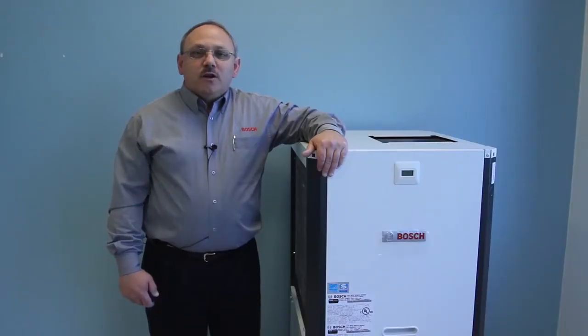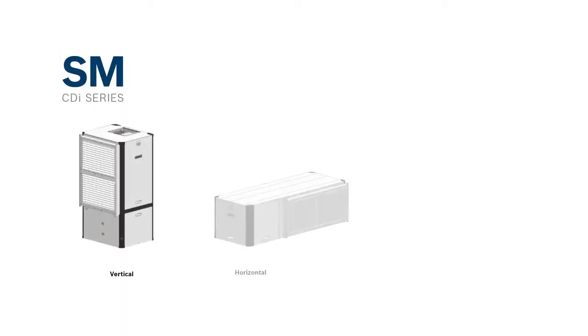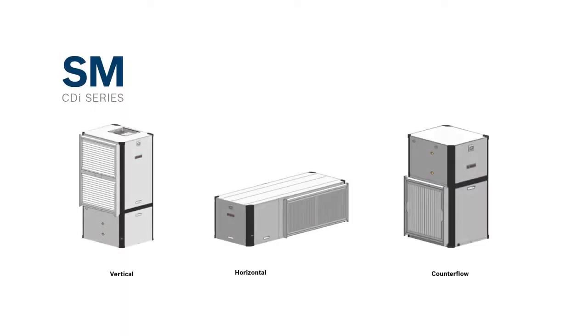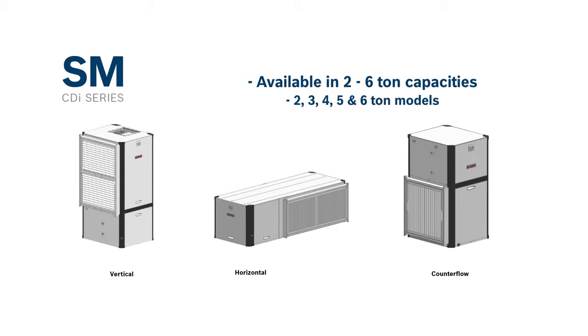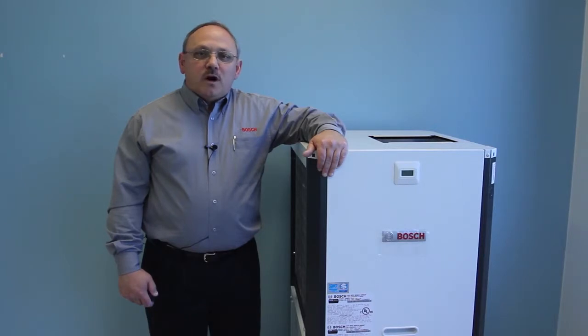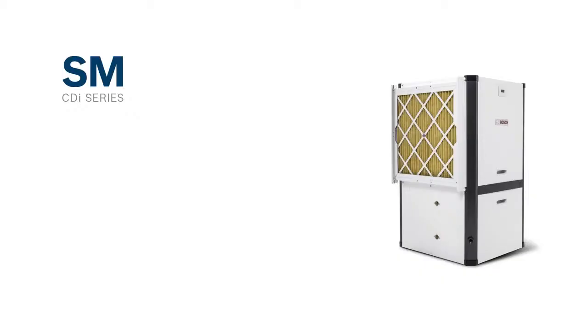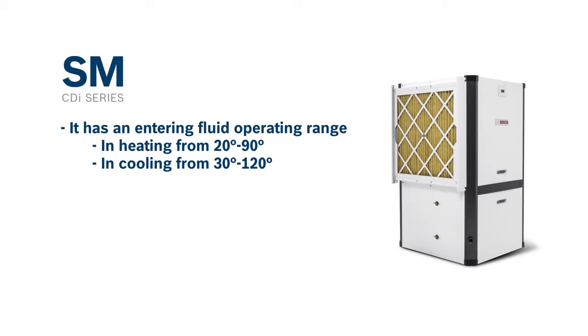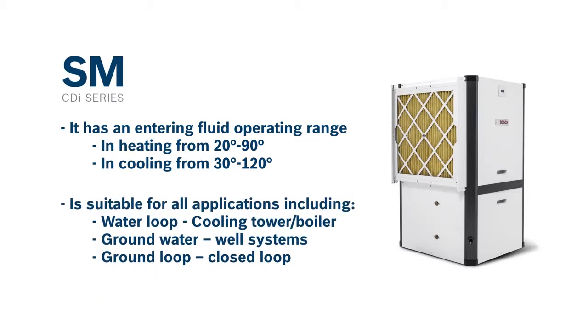It is a water-to-air heat pump. It is currently available in vertical, horizontal, and counterflow package models. It is available in capacities from 2 through 6 ton, and this video will cover the vertical model you see here today. It has an entering fluid operating range in heating from 20 to 90 degrees, in cooling from 30 to 120 degrees. It is suitable for all applications, including water loop or cooling tower boiler applications, groundwater or well water systems, and then the ground loop, closed loop applications.